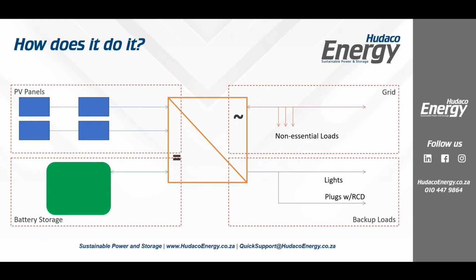The second thing it does is it looks at the current, and as long as current is flowing in this direction, from right to left, in other words, into the inverter, I know that I'm okay to not curtail my PV. As this current approaches 0 and potentially starts to move from left to right, in other words, exporting, I curtail my PV production so that I can still feed my non-essential loads with my own solar power or my own batteries, and I still meet all the compliance of not feeding back to grid. Okay, this is really, really important because it allows your return on investment to be far superior to a lot of other systems that don't have that option.